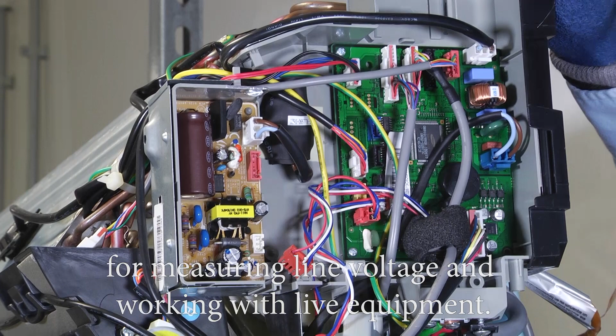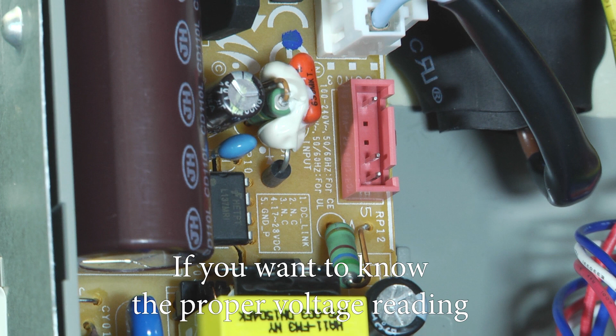As we're measuring here, we're going to refer back to the box. We're going from pin number 1 to pin number 5, which is our DC link voltage. If you want to know the proper voltage reading you should get, multiply whatever you're getting for line voltage times 1.43, so your measurement should be pretty close to that.